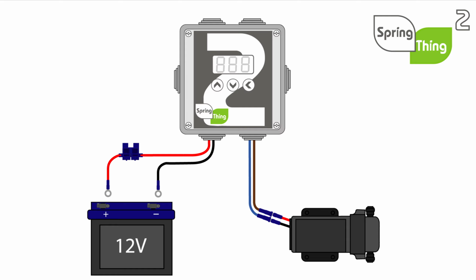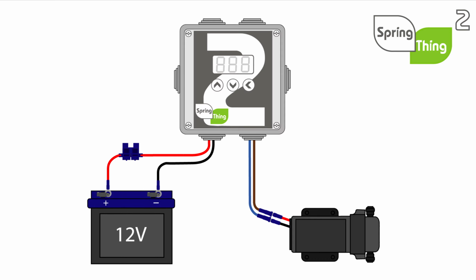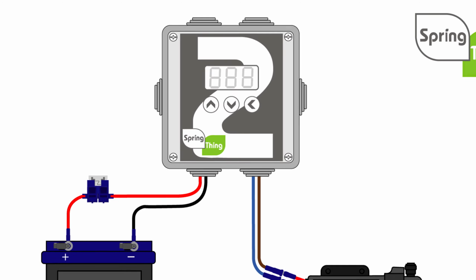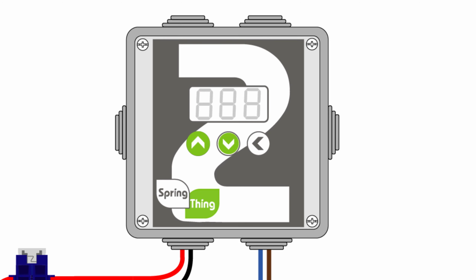Connect the red wire to the positive battery terminal and the black wire to the negative. Finally, fit the 7.5 amp fuse. Fuses should only be fitted once all connections have been made. To turn on the controller, press and hold the up or down button. To adjust the flow rate, use the up and down buttons as required. The flow rate can be set from 0 to 99.